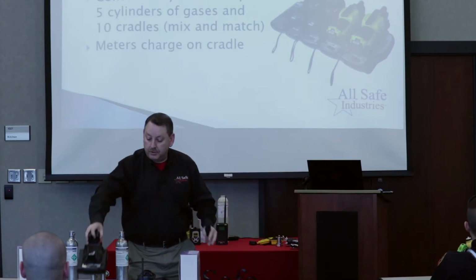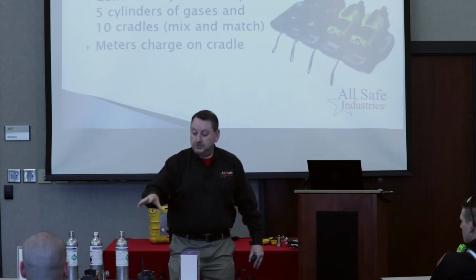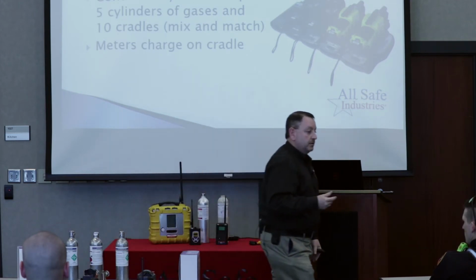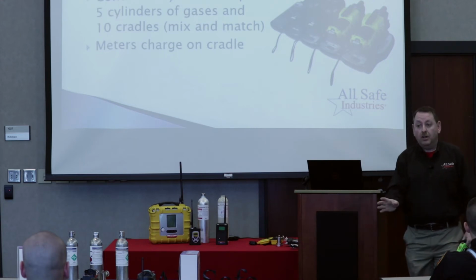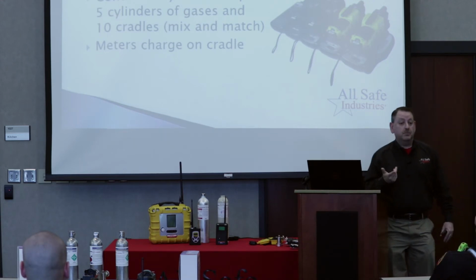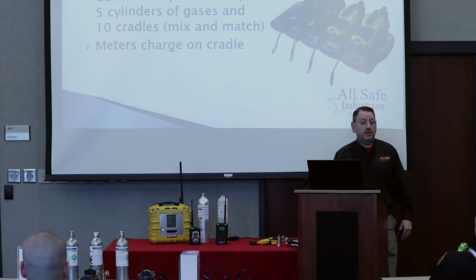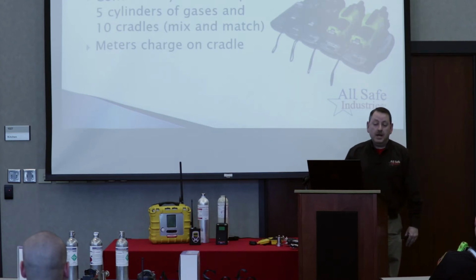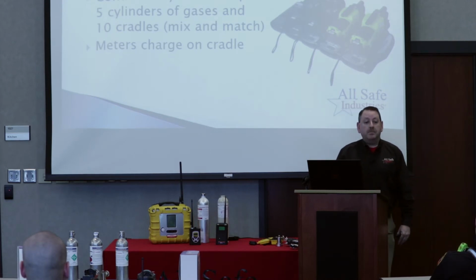This is what we call cradle-only mode. So you'll have cylinders connected directly to that to feed the gas to the instrument. It's all automatic. All you guys have to remember how to do is push the button, whether you want to do a bump check or a full calibration. The cool thing is if it fails a bump check, the cradle will automatically jump over and calibrate the meter for you. So it's really super easy to use.